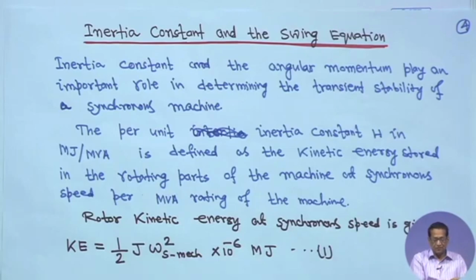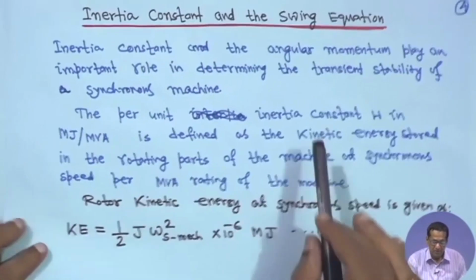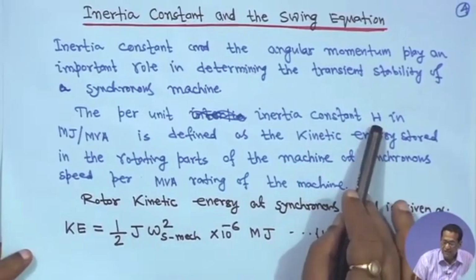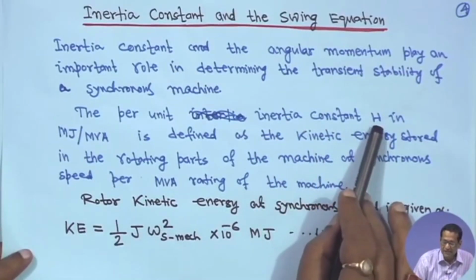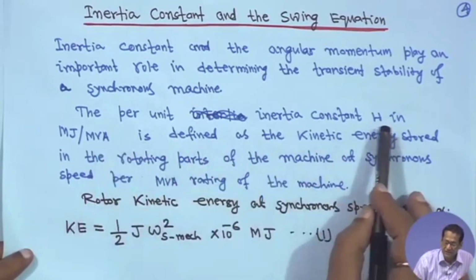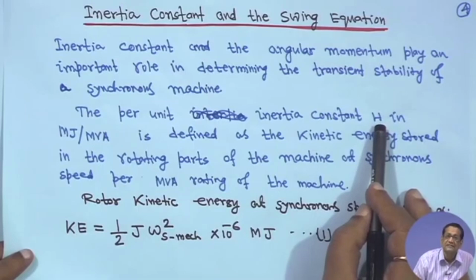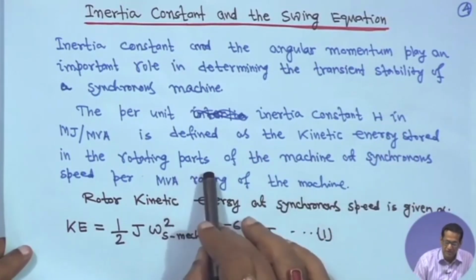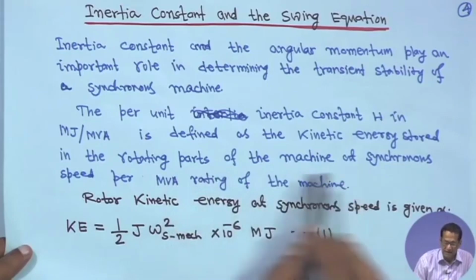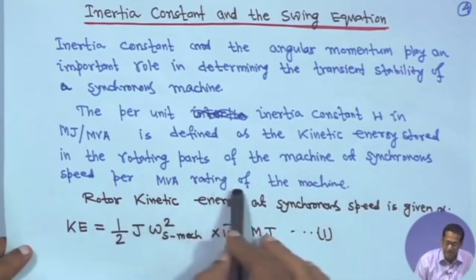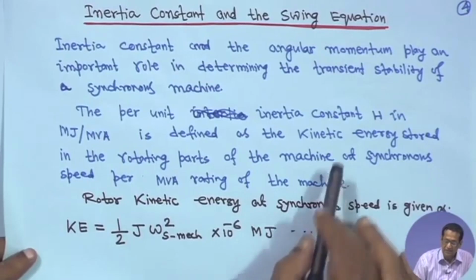So we define the per unit inertia constant H. Its dimension is megajoule per MVA, or it can be given in seconds also. It is defined as the kinetic energy stored in the rotating parts of the machine at synchronous speed per MVA rating of the machine.